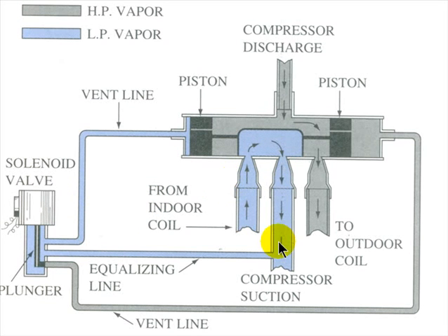Essentially, what's going to happen? The gas is going to, at some point in time, either enter or exit this cylinder part, where the rest of the gas is going to be surrounding the cylinder. Now, when the gas enters the cylinder, if it's high-pressure gas, you see this slide. Now, picture this whole thing is round. So this thing looks like a plunger, if you will, on this end, and a plunger on this end. And you see you have the slots in here?